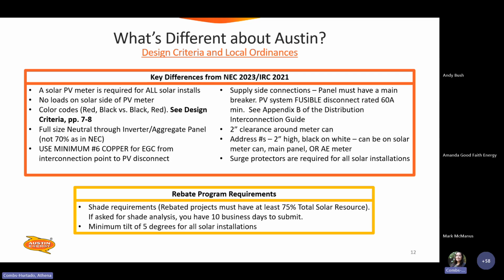Full size neutral through inverter aggregate panel, not 70% as in the NEC. Please use a minimum number 6 copper for EGC from the interconnection point to the PV disconnect. Supply side connections, panel must have a main breaker. PV system fusible disconnect rated 60 amp minimum. And then please see appendix B of the interconnection guide.